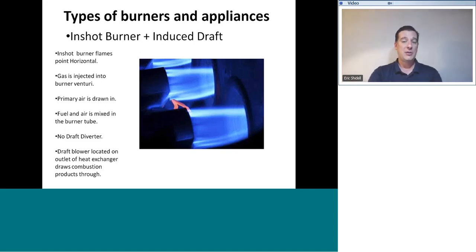Once again, just like the natural draft atmospheric burner, gas is still injected into the burner venturi. The primary air is still drawn into the venturi by the same forces. Fuel and air are still mixed in the burner tube. There is no draft diverter, however.